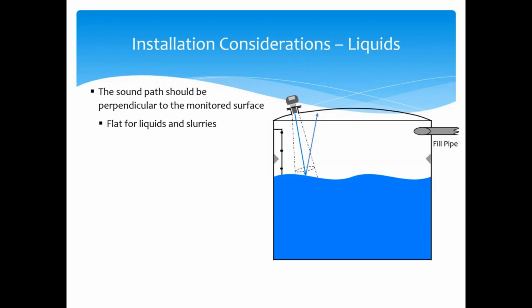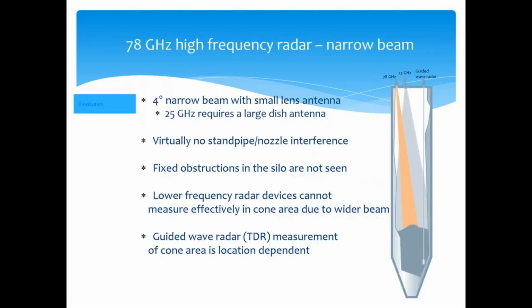One other thing to keep in mind, which I see quite regularly on dome top or parabolic tanks, is you want your transducer to be perpendicular with the flat liquid level below it. I know we show it as wavy here, but this should typically be a flat surface. So you want to make sure your nozzle, or however you're mounting it in the top of that tank, allows us to mount the face of this transducer perpendicular. Otherwise this would cause issues because we'd reflect at an angle and wouldn't get enough signal return back up to the instrument.